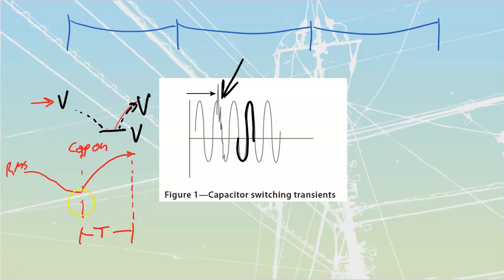If the regulator sees that the cap has brought the voltage too high for too long, it will change the transformer regulator and drop the voltage back down to where it needs to be.